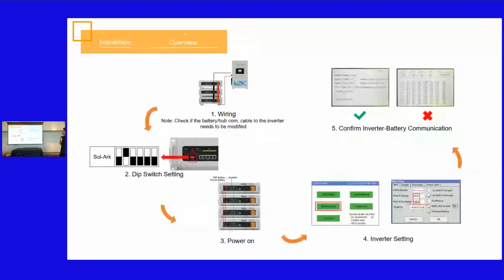Let's review the overview of the whole installation process. Step 1: wiring, connecting the power cable and communication cable. Step 2: set the dip switch according to your inverter. Step 3: power on the battery. Step 4: modify the inverter setting. Step 5: confirm that communication is successful between the inverter and the battery.